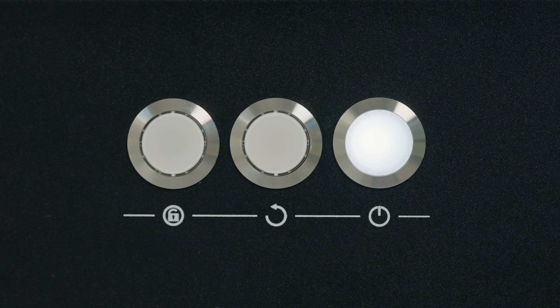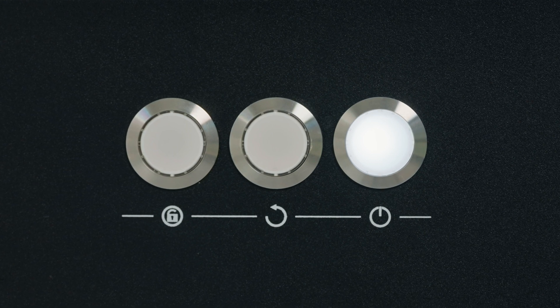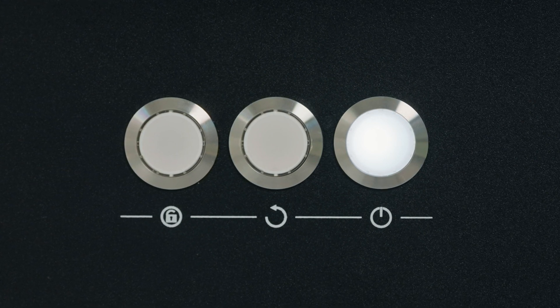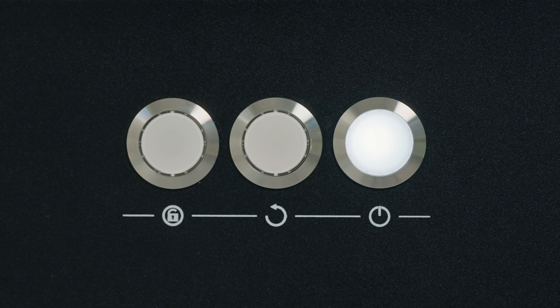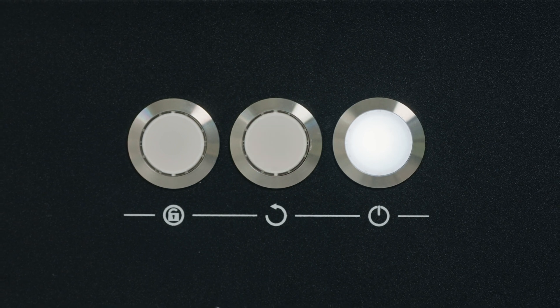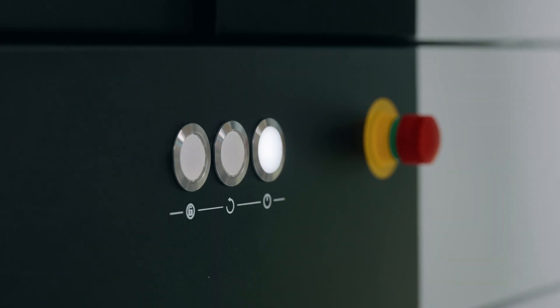Continuing to the right, we notice three buttons. The first has a lock symbol underneath — when this is lit up the door is locked and ready for use. You must press this whenever you wish to unlock and open the door. The next button is the refresh button, which you should see flashing now. This indicates the system has completed its initial power-up cycle and is ready to carry on with the warm-up. Let's go ahead and press it now. You'll need to press this button anytime you close the door, which will lock the door and prepare the system to begin scanning.